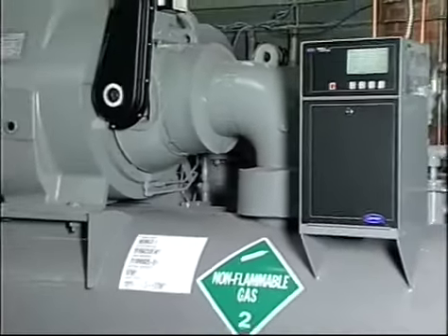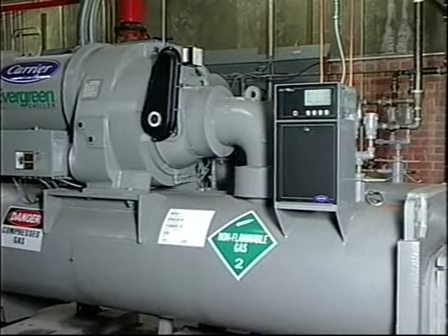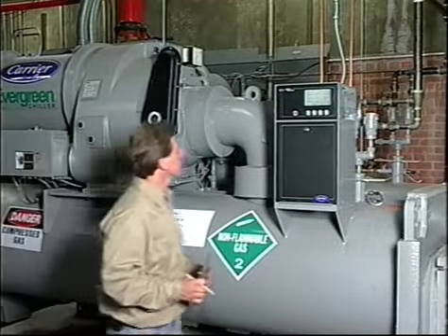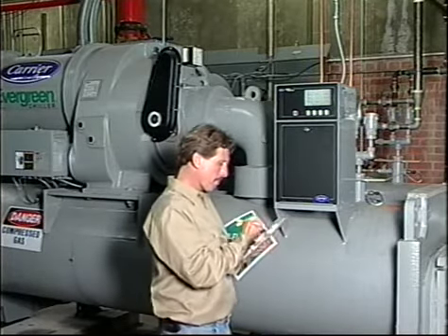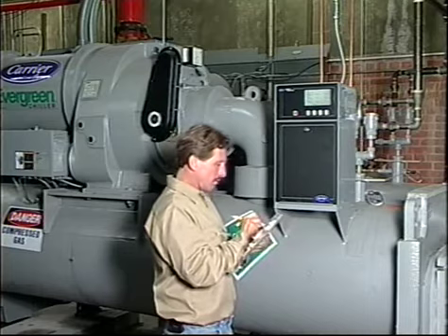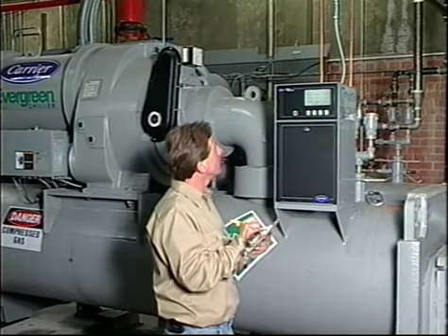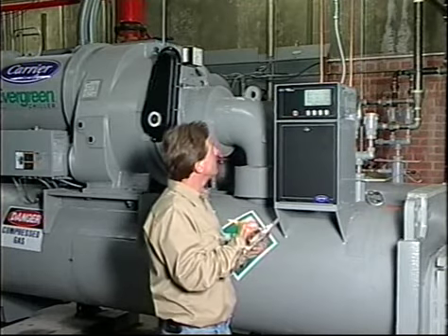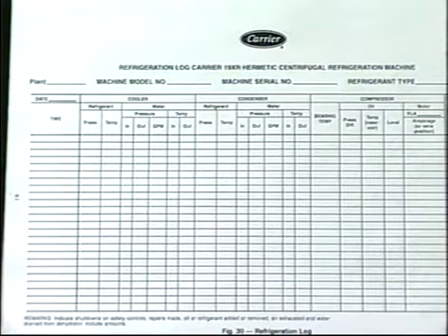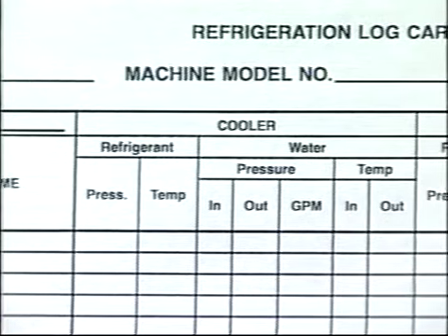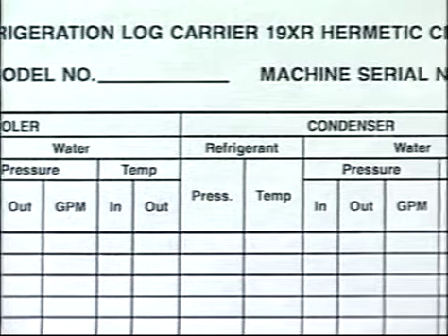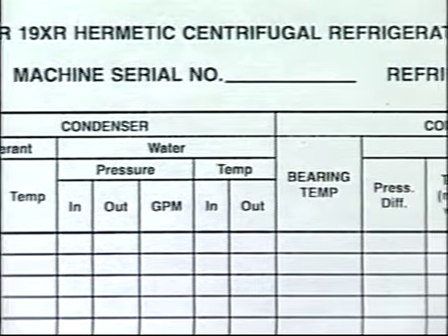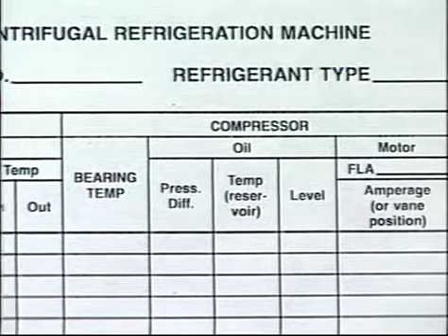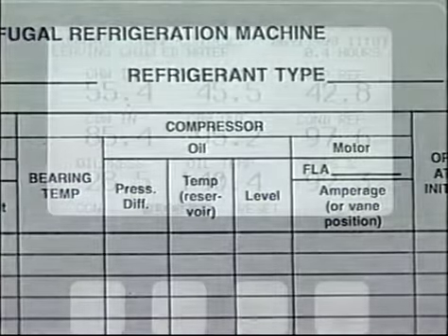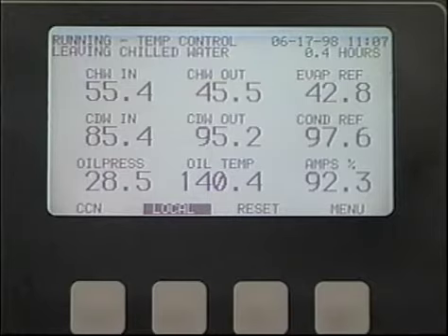One of the operator's most important jobs is to spot any problems before they become serious. So the machine's operating characteristics should be checked and recorded at least once a day, preferably at the same time each day, on an operating log sheet. The PIC controls make this very easy to do because most of the important data can be read directly from the default screen. A typical log sheet will have provision for refrigerant temperatures and pressures, chilled water temperatures and pressures, condenser water temperatures and pressures, compressor bearing temperature and compressor oil pressure and temperature, and motor amps. This information can be obtained from the LID default and status screens.